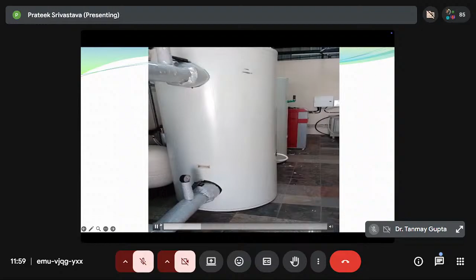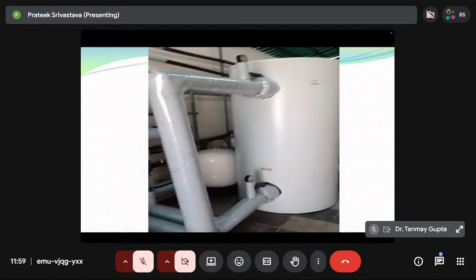If you see the backside, this is an expansion vessel. Usually when we do chilled water installations, we put expansion vessels, because when we do heating and cooling, the volume of the water changes because of thermal expansion and contraction. To avoid that expansion stressing the pipes, this expansion vessel works to accommodate it. Then we have these two tanks. One is for chilled water and another one is for hot water.